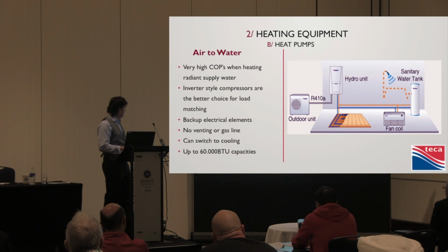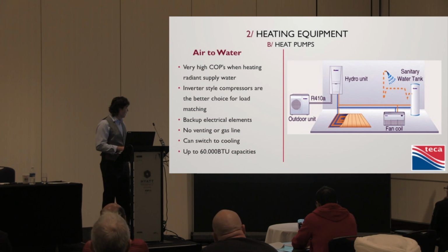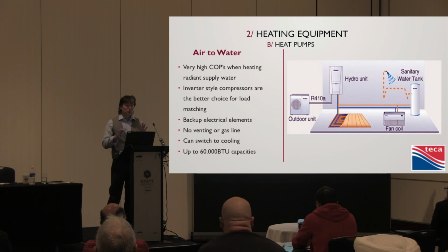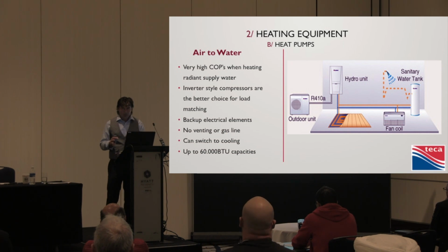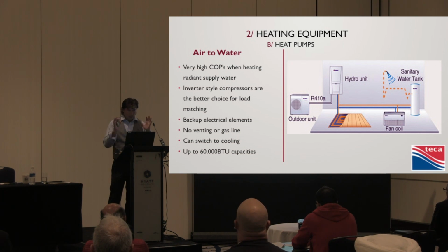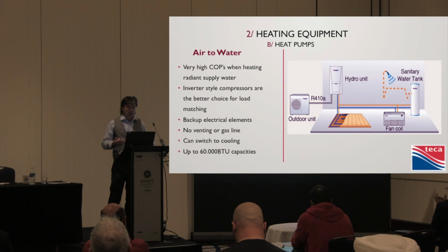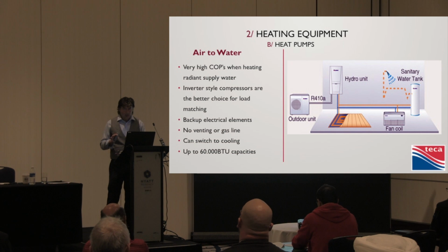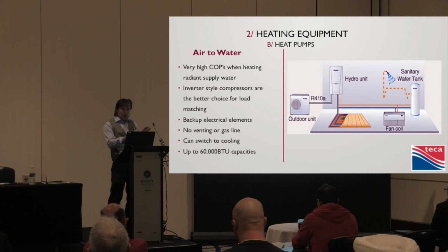Oh, inverter style compressors. Hey, so that is an inverter compressor, and this goes for all heating and cooling equipment when it comes to heat pumps. Inverter style compressors: most of the Asian units, Japanese stuff, your Mitsubishis, Daikin, Fujitsu, all the rest of it, have gone to inverter-style compressors. So if you have, say, a 5-ton, 60,000 BTU compressor, the old-school way, sitting outside, when that thing comes on, you hear this click, and the lights dim a little bit, and the compressor comes on.